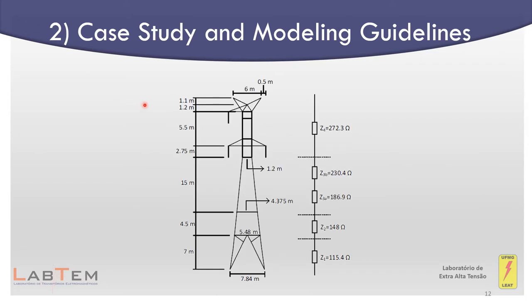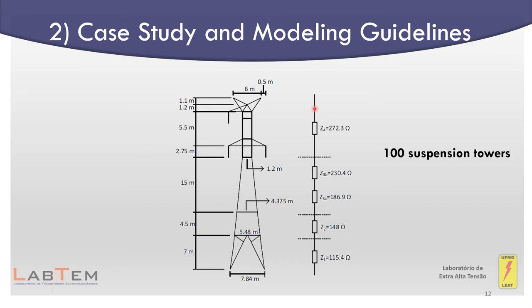In this slide it is possible to observe on the left the suspension tower geometry and the ATP tower model on the right. The tower was divided into five sections, each one represented by four conductors. This was done to consider the variation of the cross-section of the tower with position, which changes the mutual surge impedance as a function of height. 100 of the 220 structures are suspension towers.